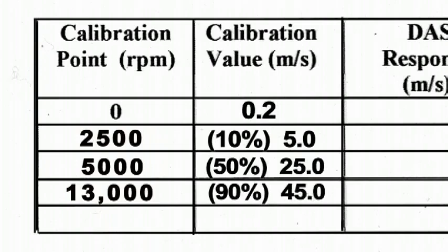The next step is to begin the zero test of the sensor. This is a simple test. With the cups removed from the sensor, have the technician record the output of the sensor on the DAS. The zero point will not be zero. It will be the starting threshold of the anemometer. This value will be in the manufacturer's manual.